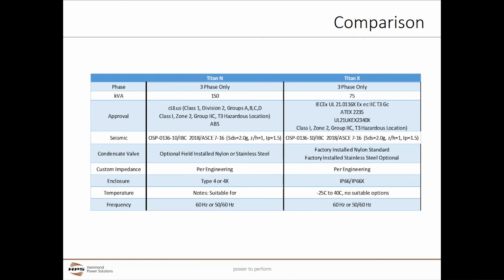The standard enclosure for our Titan N, as it is used in the North American market and defined by NEMA standards, is either type 4 or 4X. For Titan X, we follow a more international rating for the enclosure, and those types correspond to either IP66 or IP66X, that's equivalent to stainless steel.